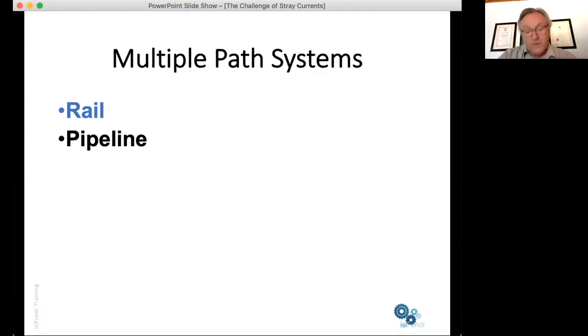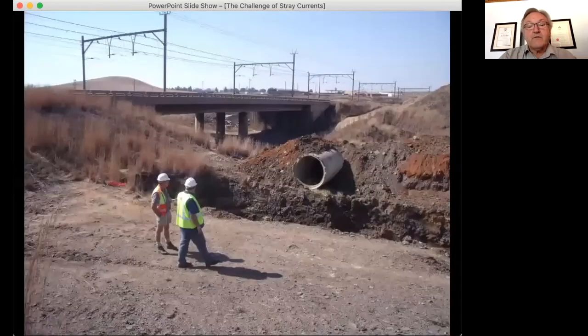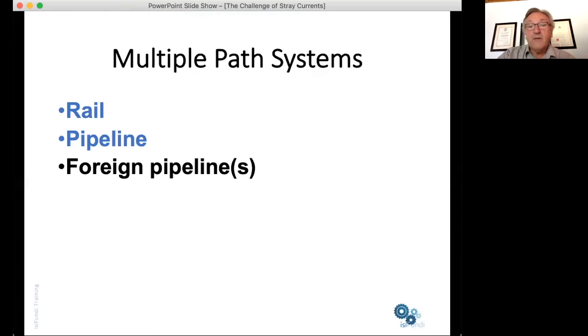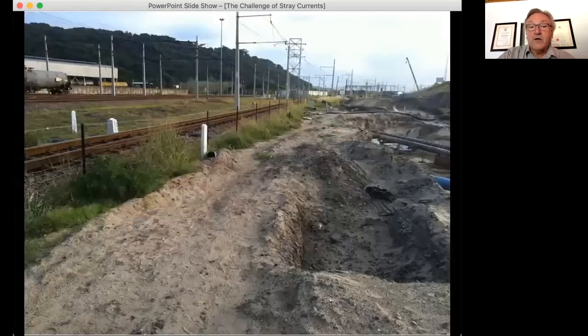However, when there's a pipeline in the ground nearby, some of that return current picks up the pipeline and follows it. But what happens if that pipeline doesn't go back to the same location as the traction substation? Maybe it goes via somebody else's pipeline. Here you can see a situation with a number of different pipelines interacting with the rail system, so stray currents can jump from pipeline to pipeline.